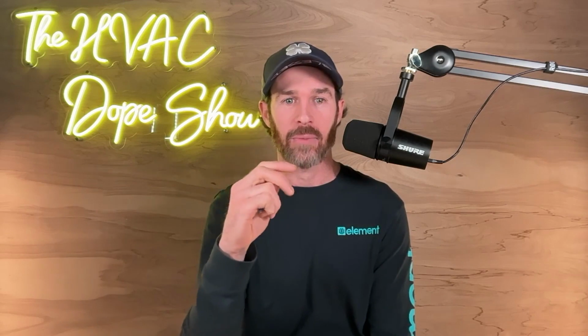I love the filter debate, we can always get into it with filters. People have asked me out here, you know, we'll see the classic case of the 1-inch MERV filter. Someone throws it in and it trips the system on high limit, or causes system icing in the summer. They always ask me, well, why do they sell these then? And I honestly don't know, because we don't get the best airflow out of them. We're at altitude, so it's a little different, air is already thinner here, and I think that maybe makes it worse.